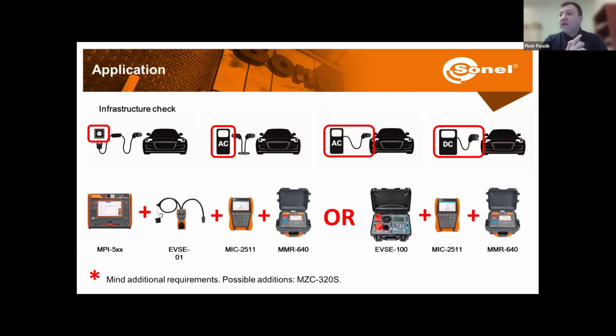Now, optionally, in case the charging station is very close to a transformer, we will expect the fault loop impedance to have very low values. And in such a situation, we will need a more precise fault loop impedance meter, like, for example, here, the MZC320. But let's say this is just optional. It all depends on the circumstances and the design of the network.